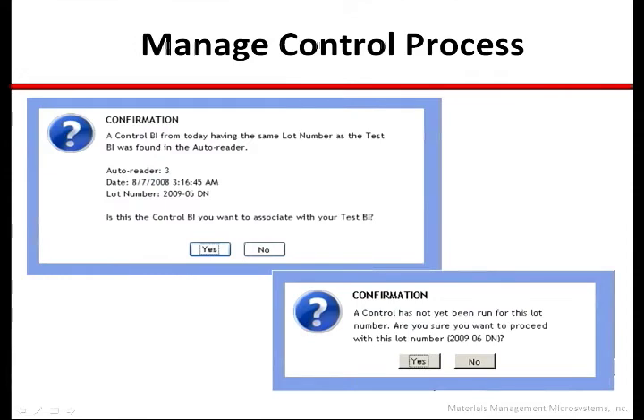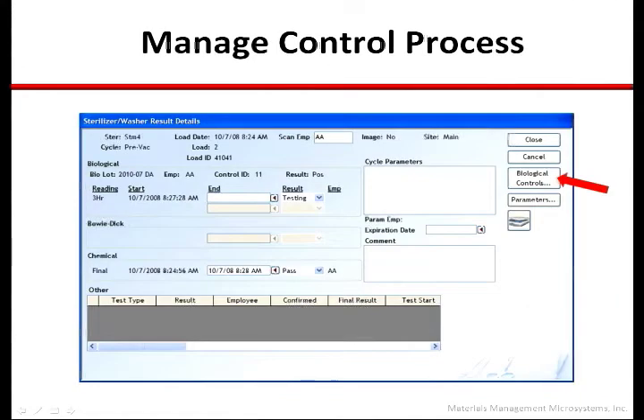When the lot number from the test BI is entered, the system will try to correlate that to a control BI with the same lot number in the same auto-reader for that same day. If one has already been recorded, the technician will be prompted to confirm they wish to use that control BI. If one is not found, then the technician will be prompted to run a control BI for that lot number, auto-reader, and day. The system speaks to the recommended practice for control biologicals — that one is required for each lot number, for each auto-reader, for each day. The system will recognize when a control is needed based on the auto-reader in which the test BI was placed.